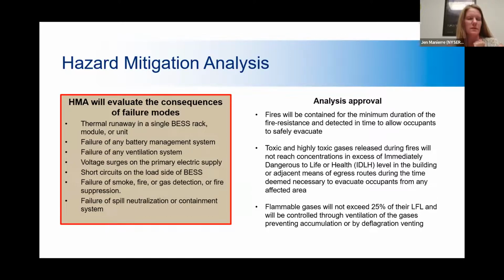So those larger ones are going to have to go through a hazard mitigation analysis before being approved. That analysis will look at, if there are failures that happen in the system, what are the consequences of those failures? And is it a reasonable risk, and it'll be okay, right? That's what this hazard mitigation analysis is trying to do. So it'll look at what happens if there's thermal runaway in a single energy storage system rack or a single energy storage system module. What will happen if the battery management system happens to fail? What will happen if the ventilation system fails? What if there's a voltage surge or a short circuit? What if the smoke, fire, or gas detection fails, et cetera?